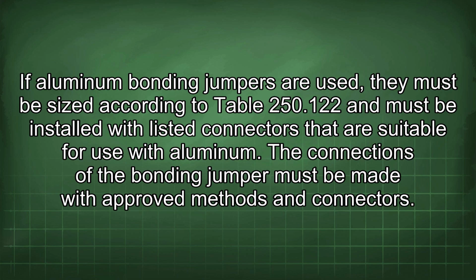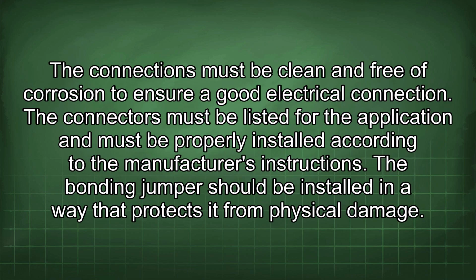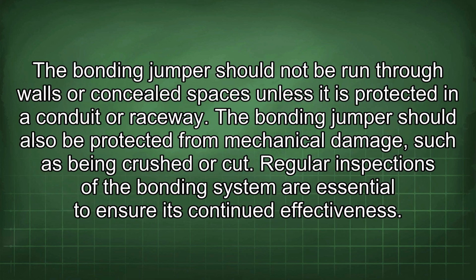The connections of the bonding jumper must be made with approved methods and connectors. The connections must be clean and free of corrosion to ensure a good electrical connection. The connectors must be listed for the application and must be properly installed according to the manufacturer's instructions. The bonding jumper should be installed in a way that protects it from physical damage. The bonding jumper should not be run through walls or concealed spaces unless it is protected in a conduit or raceway. The bonding jumper should also be protected from mechanical damage, such as being crushed or cut.